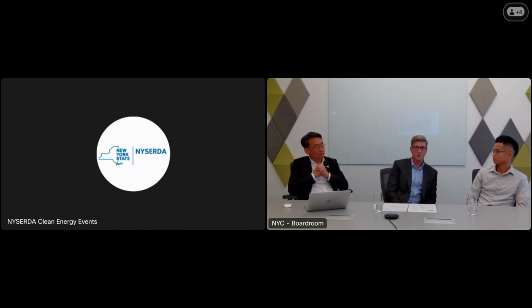So over at the Josie Robertson Center, we chose to clear the surge map because we never saw the chiller operate below that 50 hertz level. It is a York YK chiller. They are fairly efficient machines.